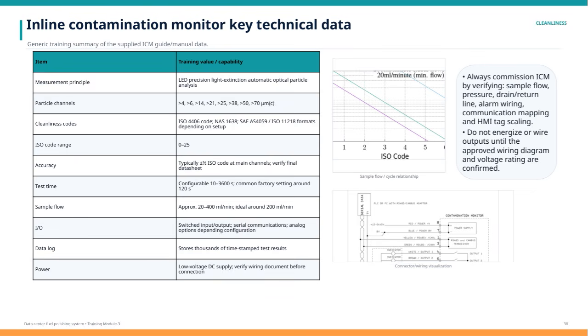Always remember, when commissioning the ICM, to verify parameters like sample flow and pressure, ensure proper drain and return lines, check alarm wiring, confirm communication mapping, and scale HMI tags correctly. Do not energize or wire any outputs until the wiring diagram and voltage ratings have been fully approved. This comprehensive approach ensures the ICM operates reliably, providing accurate contamination monitoring that's vital for maintaining fuel polishing system cleanliness and overall equipment health.